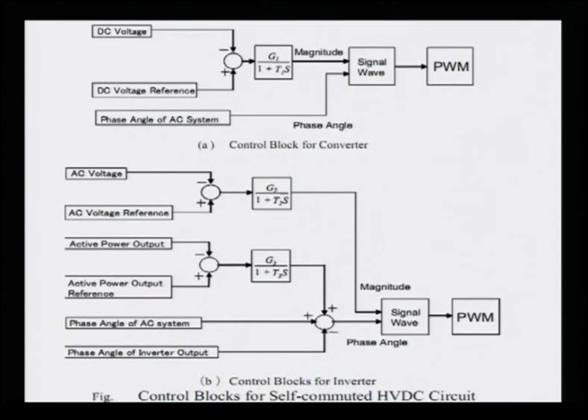Also, HVDC Light has the capability of controlling active and reactive power respectively, and it can support the AC voltage and the DC voltage during a fault in the power system. So, in the multi-infeed HVDC system, HVDC Light can help the recovery of the HVDC system and prevent commutation failure of these HVDC systems. Again, if you have HVDC Light in feed with the HVDC system, it improves the power system performance, and it also improves the performance of the DC links.